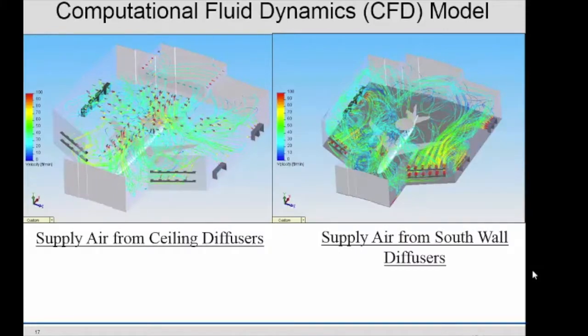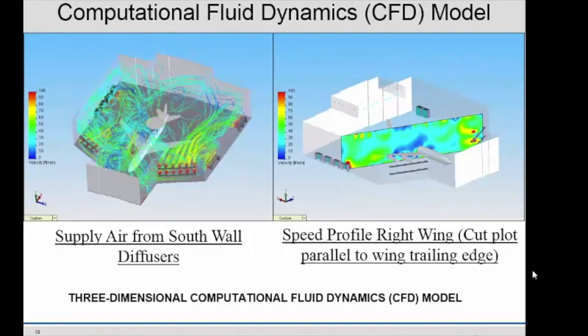CFDs, computational fluid dynamics, are required on these plane hangars because they have to have velocities of between 80 and 100 feet per minute for the paint to cure properly. So that's why they have so much makeup air: this wall of air is moving across that plane to make sure that air is maintaining around 80 to 100 feet per minute, or it doesn't cure properly.